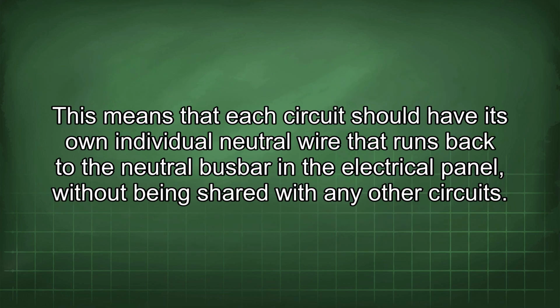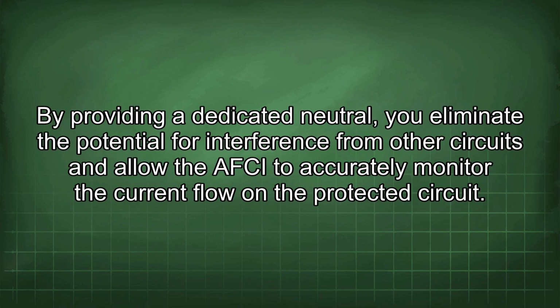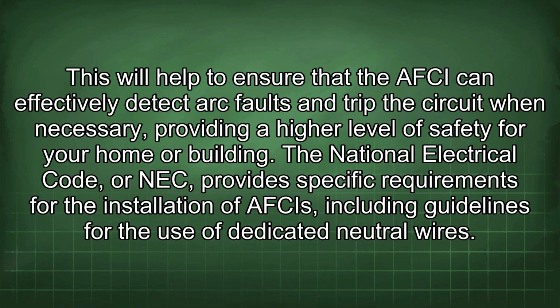This means that each circuit should have its own individual neutral wire that runs back to the neutral busbar in the electrical panel without being shared with any other circuits. By providing a dedicated neutral, you eliminate the potential for interference from other circuits and allow the AFCI to accurately monitor the current flow on the protected circuit. This will help to ensure that the AFCI can effectively detect arc faults and trip the circuit when necessary, providing a high level of safety for your home or building.